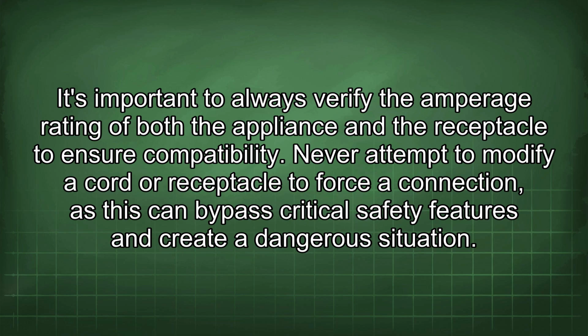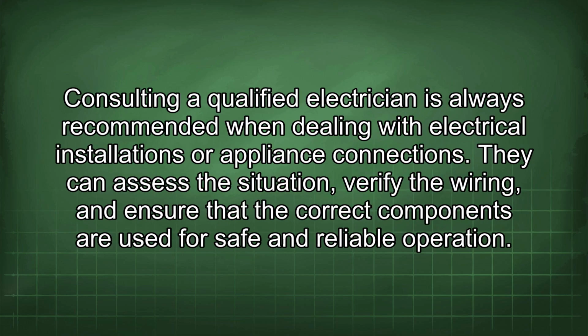Never attempt to modify a cord or receptacle to force a connection, as this can bypass critical safety features and create a dangerous situation. Consulting a qualified electrician is always recommended when dealing with electrical installations or appliance connections.